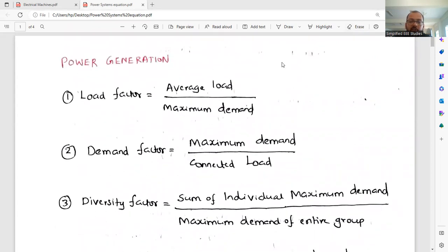Then you can see the definition of the demand factor. What is the definition of demand factor? Maximum demand divided by connected load. If I talk about the diversity factor, it is the sum of individual maximum demands divided by the maximum demand of the entire group. Remember, load factor will always be less than 1, whereas diversity factor will always be greater than 1. Like that, you have to remember the important equations.